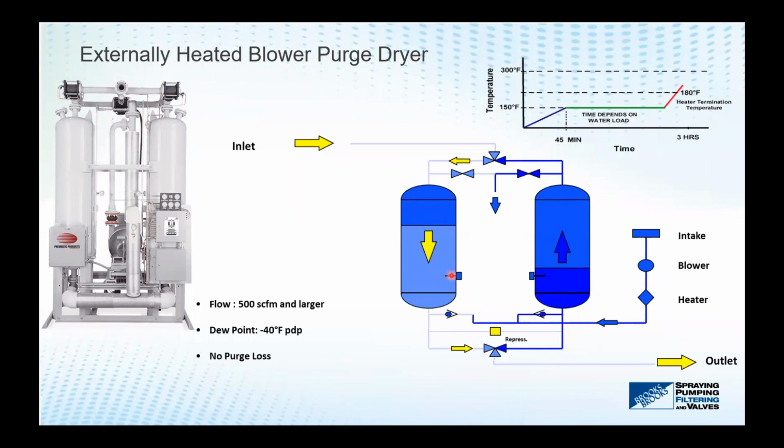So what that probe that's depicted in the chamber does is measure the moisture front as it moves down the chamber, which may move all the way down in 4 hours, depending on flows, pressures, and temperatures. It may take a few days before it needs to regenerate. So what we're doing is ultimately saving the customer energy. And we'll talk about that a little bit more in the next webinar.